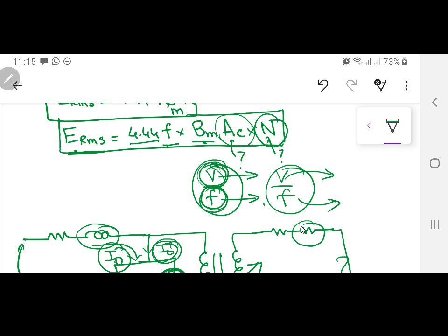And whenever you are designing a transformer, either a core type or a shell type, near the core you are always going to place the low voltage winding, because the core is electrically at neutral, it's grounded. आपको नहीं चाहिए कि your core should have some current flowing through it. There will be some electrostatic current flowing over there. To avoid that electrostatic current and to keep that transformer insulation small, you will first of all place the low voltage winding, then some insulation, then maybe an oil duct, because if it is going to be immersed in oil, and then the last is the high voltage winding.